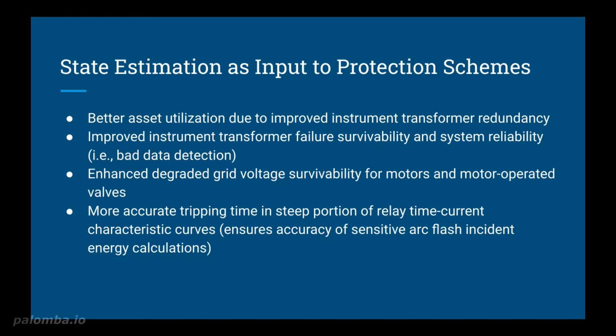And in addition to this, the operability of motor operated valves is a great concern of the NRC as well. Protections of the motor operated valves can be enhanced by incorporating the open or closed state of the valve, by inputting the state of their associated limit switches into the state estimation protection system. And in light of nuclear safety, the overload protection for the motor operated valve can be blocked if the valve did not successfully change states as required.